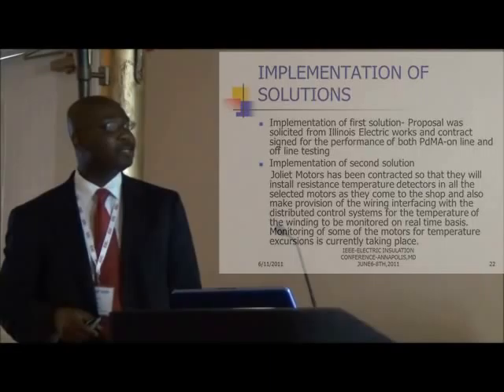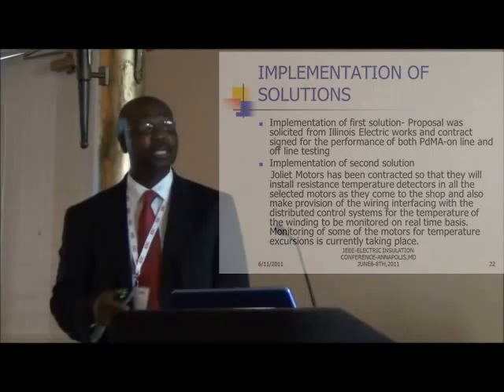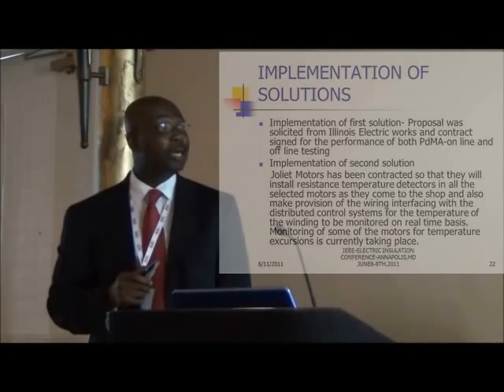For implementation of the first solution, we solicited a contract from IEW for periodic PDMA online and offline testing. Online testing is pre-outage — you gather all the motor signatures and identify which motors are going to be problematic. During the offline period, detailed offline testing is then performed on those identified motors.